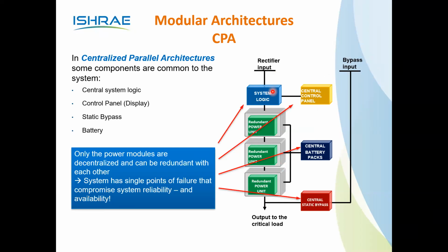In the frame, all of this is going to be assembled in one frame. It will not come in separate boxes. It will be in only one single frame. System logic will also be one box. There are three power unit boxes. Static bypass is again only one box. The control panel will be moulded in the frame. The battery bank, anyway, is external. This is how the architecture looks. It's typical. It looks like a rack mount or modular concept.